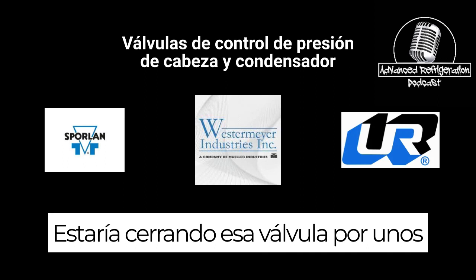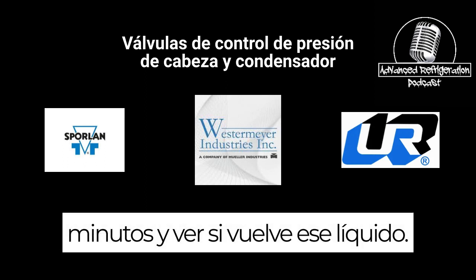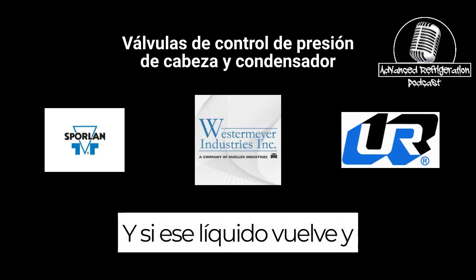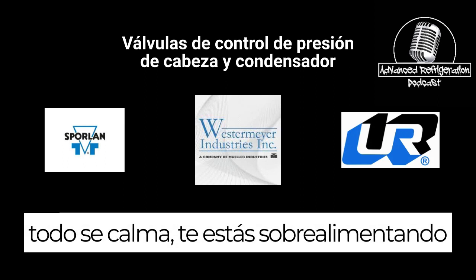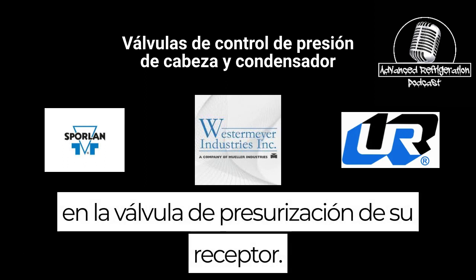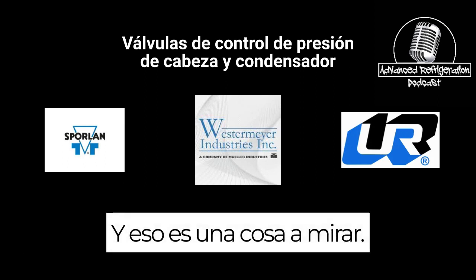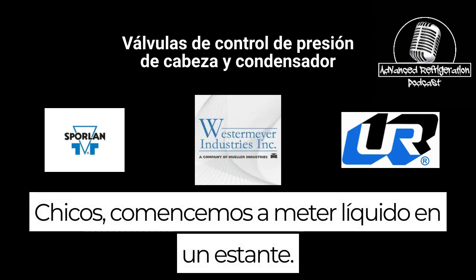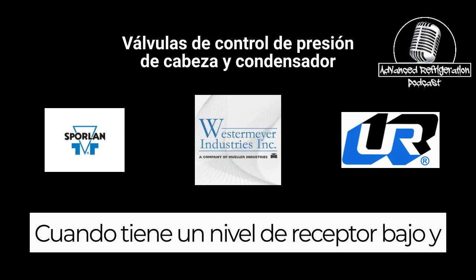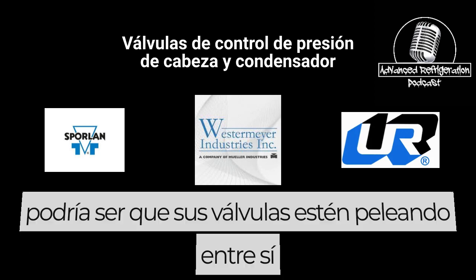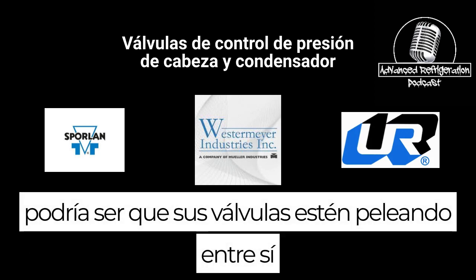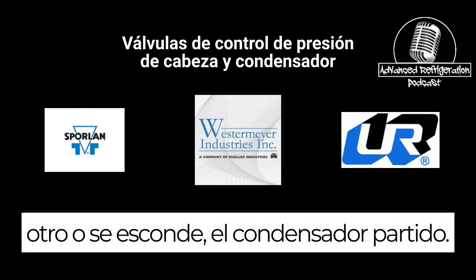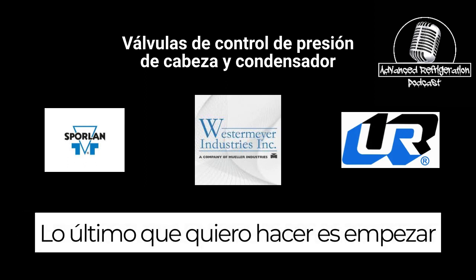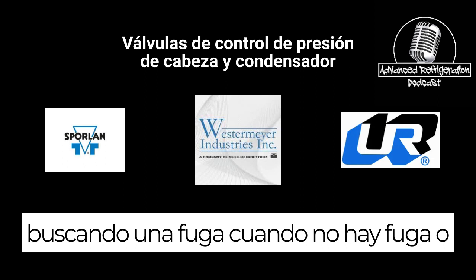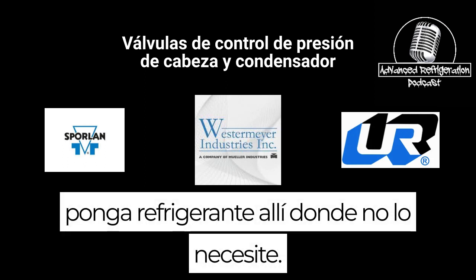I would be shutting that valve for a few minutes and seeing if that liquid comes back. And if that liquid comes back and everything calms down, you're overfeeding on your receiver pressurization valve. That's one thing to look at. Guys will just start jamming liquid into a rack when it's got a low receiver level, and it could be your valves are fighting each other or it's hiding out in the split condenser. The last thing I want to do is start looking for a leak when there's no leak, or put refrigerant in there where you don't need it.